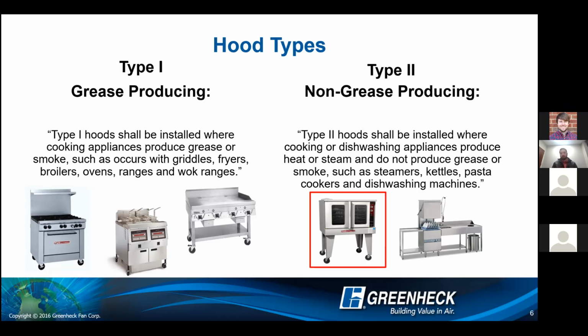In my experience, the local code authority is going to go to the worst case scenario. They're going to say, okay, it's a bakery, that's great, they're doing baked goods, but is there potential down the line that that bakery could bake a bunch of bacon and then crumble that bacon up and put it on its donuts? If that possibility exists, then most authorities are going to require a type 1 hood.